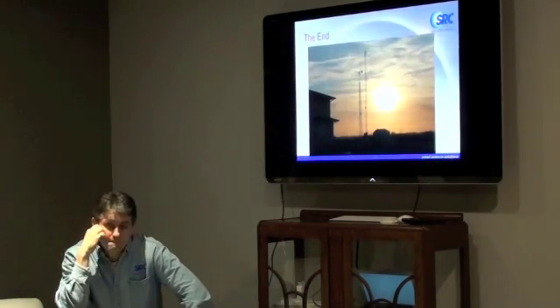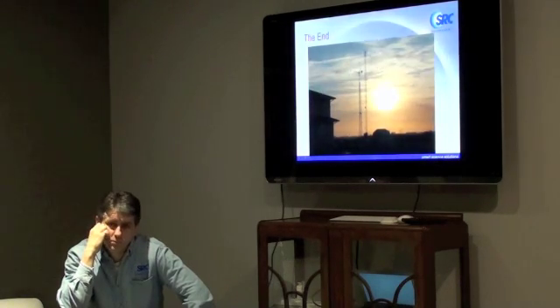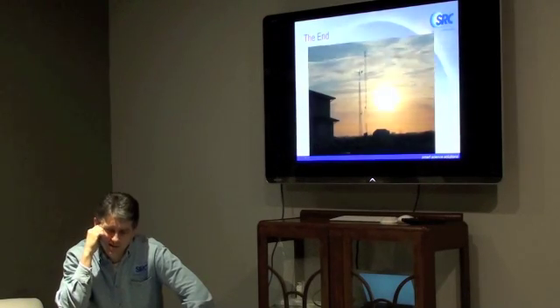One concern is you're using the same manufacturer for all the data sets. If that component isn't producing the right data, then you might be seeing skewed results across the whole thing. If you're using Kamstrup for every house, which it sounds like, I know it's the de facto solar thermal monitoring, and they use it for billing in Europe and all of that. So I know it's a good quality product, but again, we've got one on here, we're trying to monitor it now, and we've got some issues with it. Again, we're trying to monitor the glycol, so they've given us a different style of flow meter for the glycol.